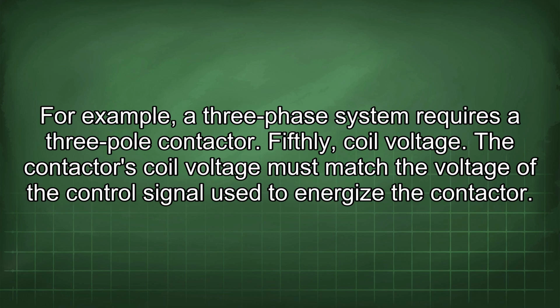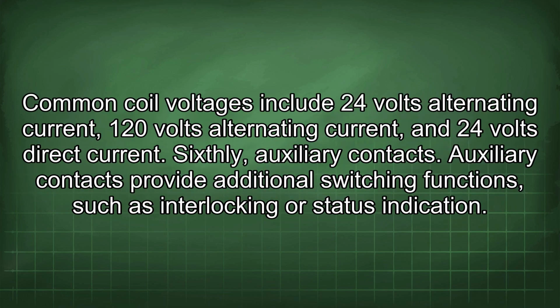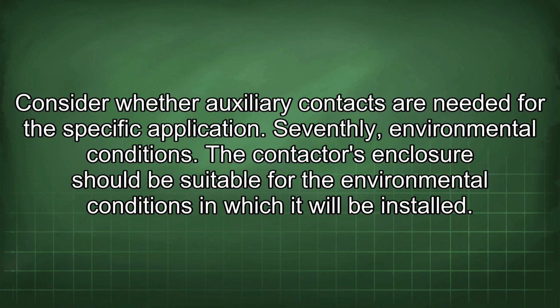Fifthly, coil voltage. The contactor's coil voltage must match the voltage of the control signal used to energize the contactor. Common coil voltages include 24 volts alternating current, 120 volts alternating current, and 24 volts direct current. Sixthly, auxiliary contacts. Auxiliary contacts provide additional switching functions such as interlocking or status indication. Consider whether auxiliary contacts are needed for the specific application.